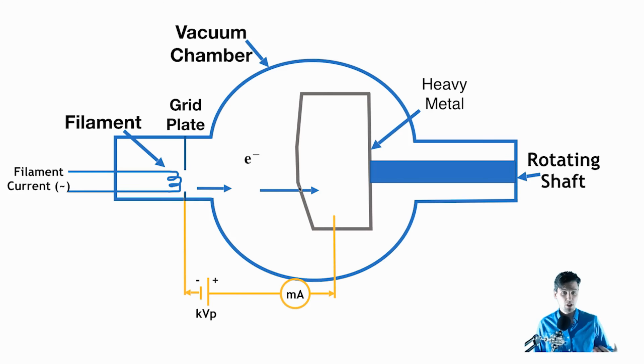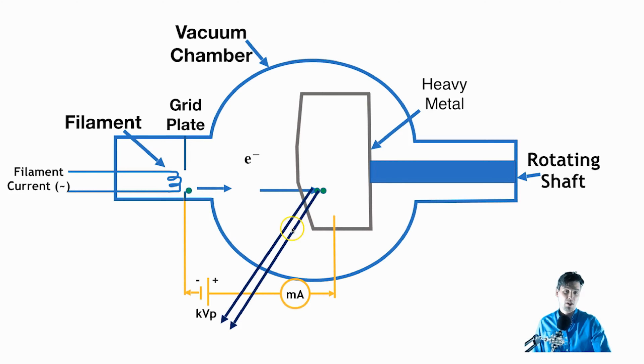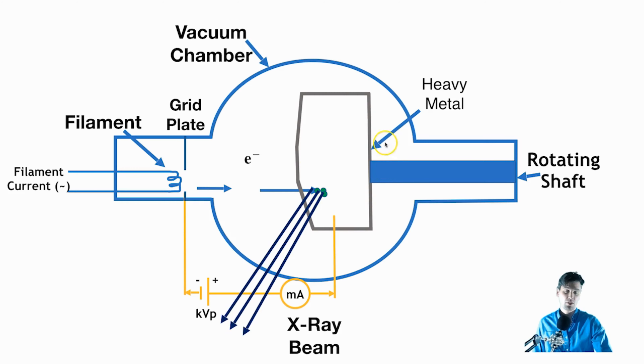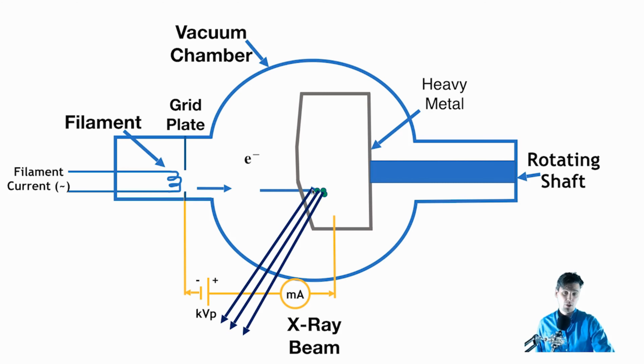In that waterfall analogy, mA is how much water is coming down the waterfall, and KVP is the height of the waterfall. The electrons will hit the heavy metal target, and then photons will come out. Electrons are coming in and photons are coming out — that's how our x-ray beam is generated with a diagnostic x-ray scanner. One concern is that the anode gets very hot from the electrons hitting it. So in modern x-ray tubes, the anode is rotating — rotating in and out of this plane about a shaft — so the electrons aren't always hitting the same spot. The anode is also called the target, and rotating it prevents any one area from getting too hot.